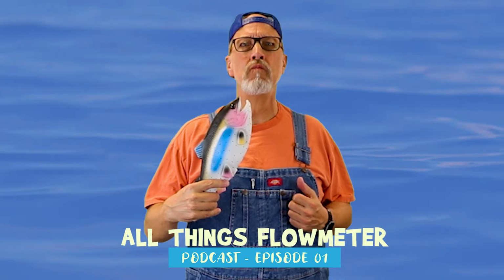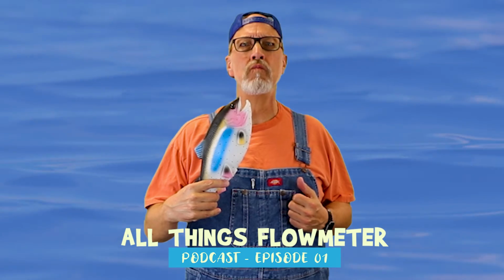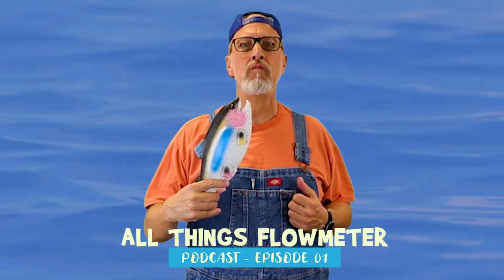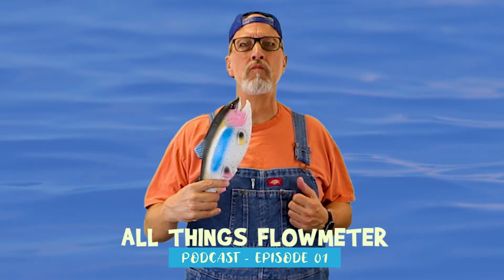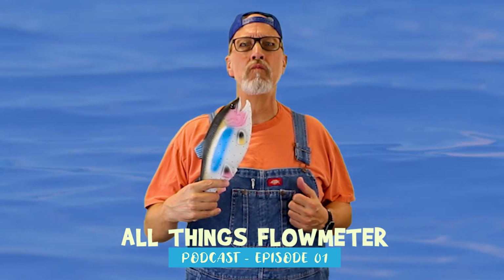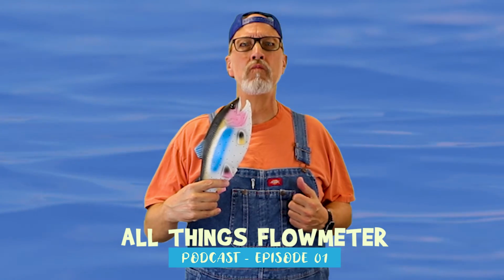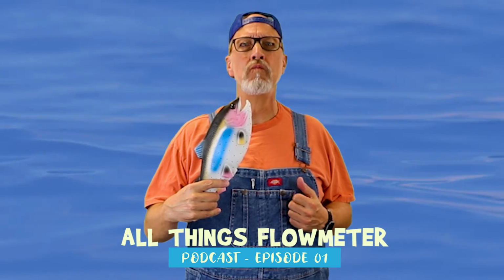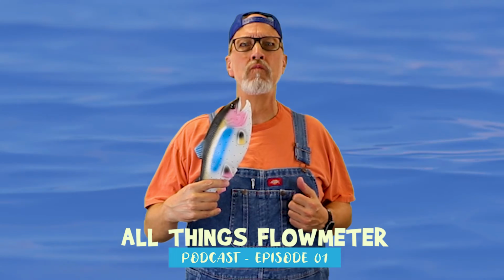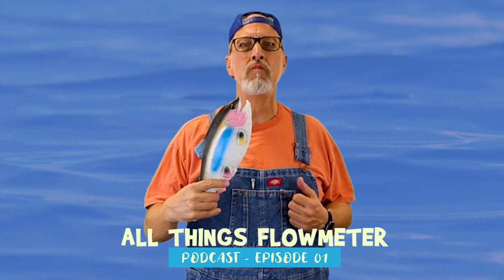Well, as far as troubleshooting steps, the first thing that happens is the meter faults, it stops reading. What's the problem with that? And that's the most common. It's a mechanical device, and obviously there's some mechanical failure. There's something in the line, something got caught up on the device there. If it's an electronic device, with mag meters or some other meters, the first thing you want to do is check the electrical ground.